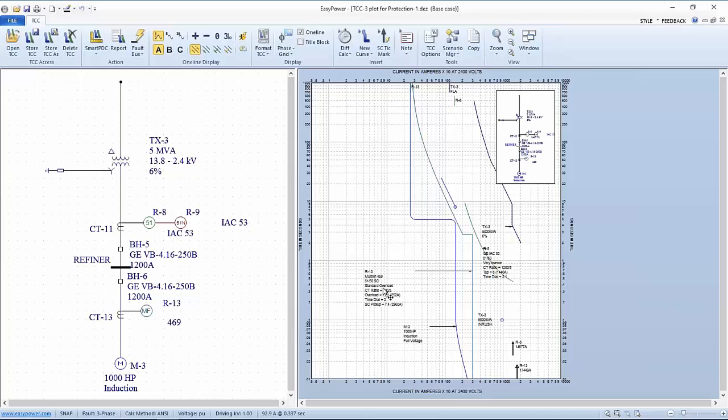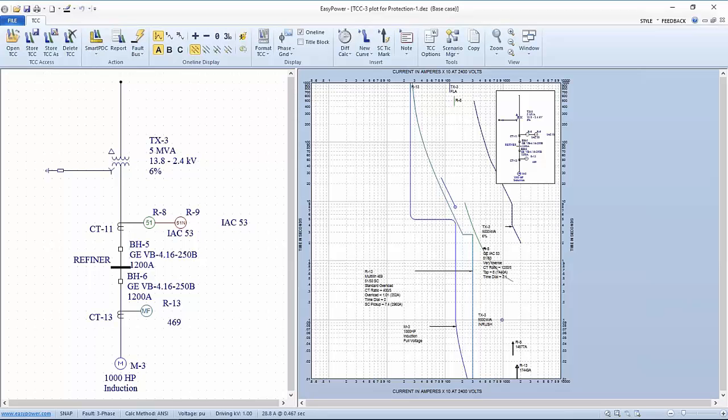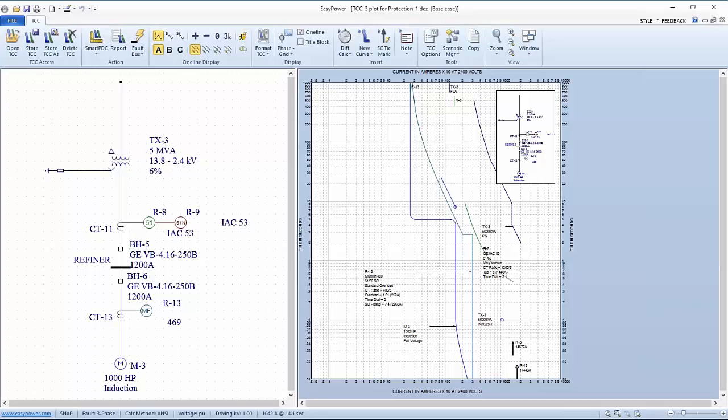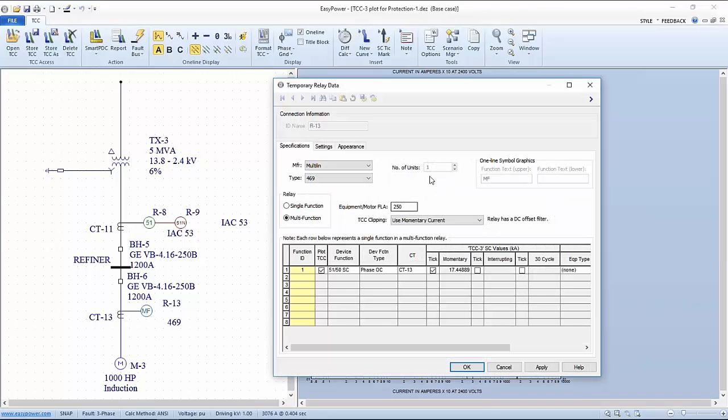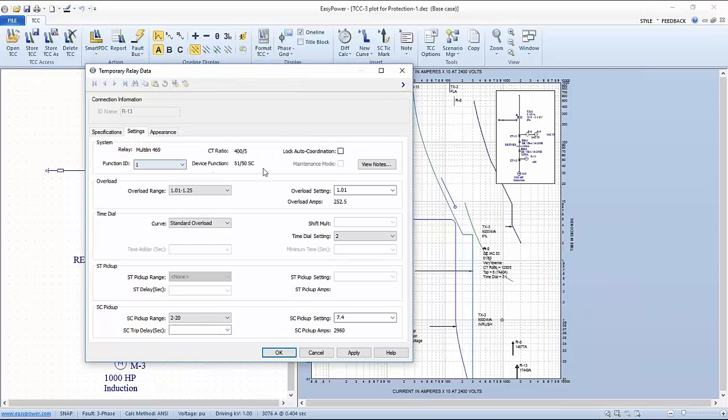Likewise, if we were to pick on the motor overload section of the setup dialog, if we pick a different value for the overload characteristics, then it will plot differently. That's, in part, how we determine whether or not the protection for the motor starting operation is adequate. Clearly we're going to run way long on time, so I'm going to cut this short and pick up the dialog at a later date. But the bottom line is that the time current characteristic curves allow us to plot on a single display the devices that need to be protected and the protective devices in their operations.